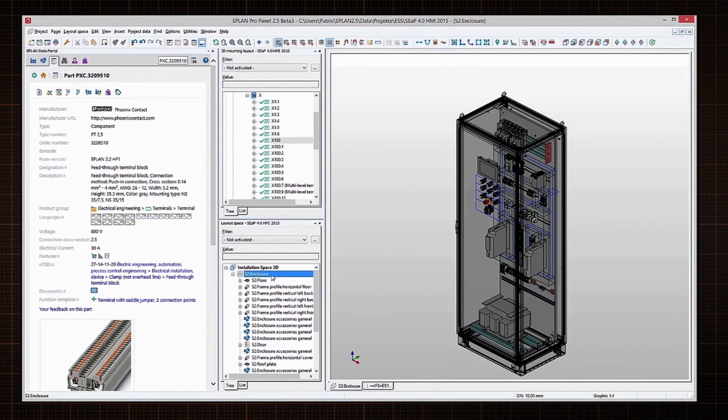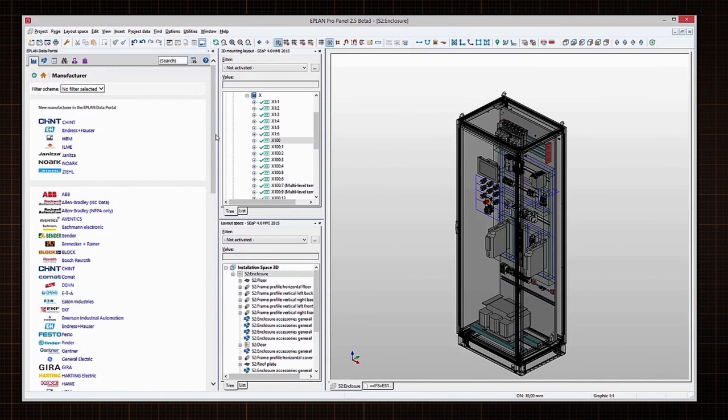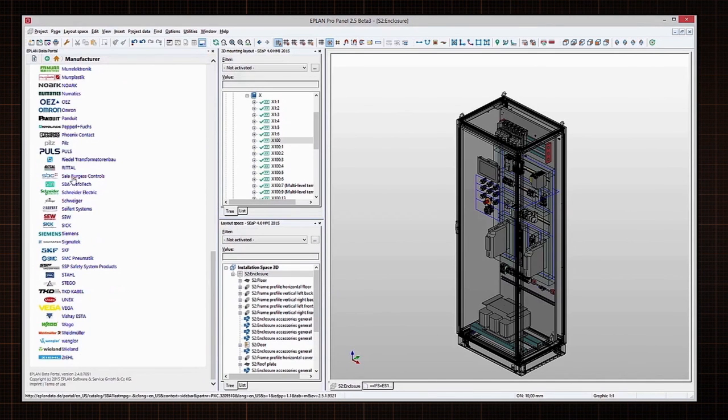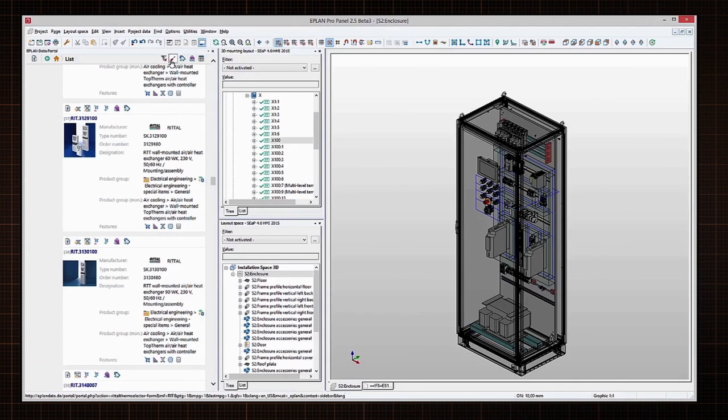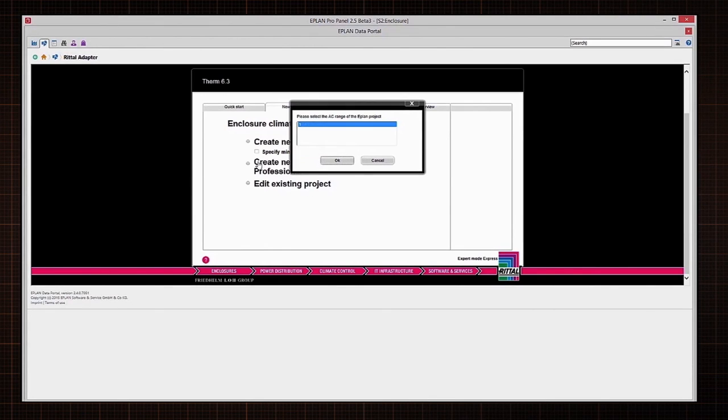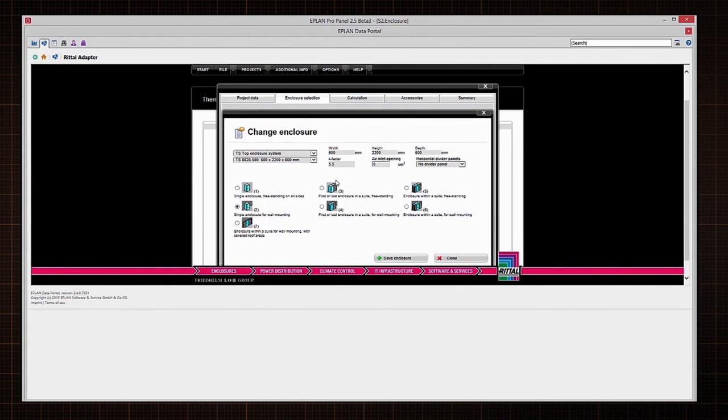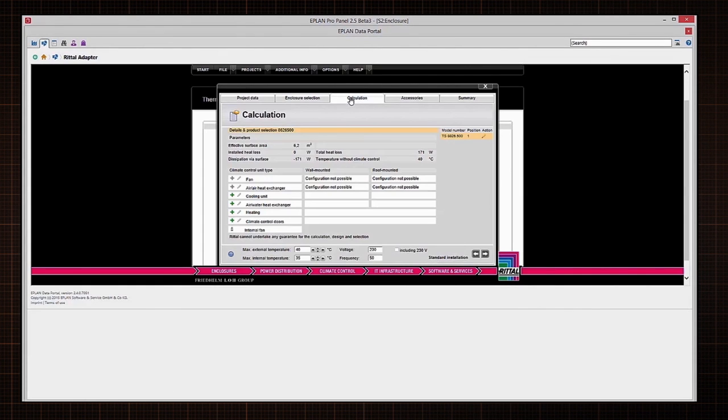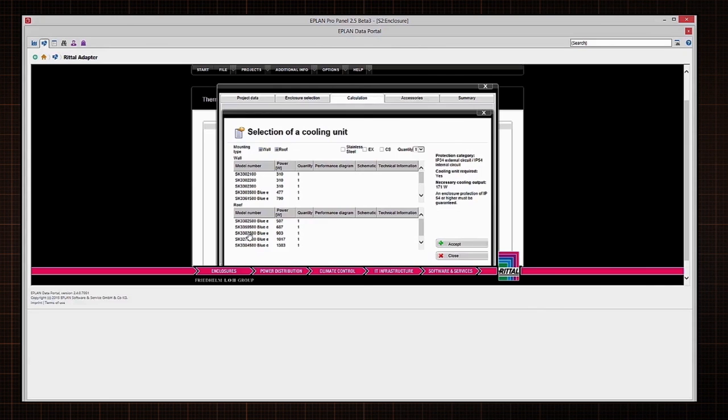Following the virtual assembly of components in the enclosure, the digital product data can be used to determine the total power dissipation of the control cabinet application. Eplan transfers this data on power dissipation plus key information on voltage, the enclosure location within the factory, interior and exterior temperatures, and nearby media to RiTherm. RiTherm is a software program used to design and size heating, cooling, and climate control solutions for switchgear.